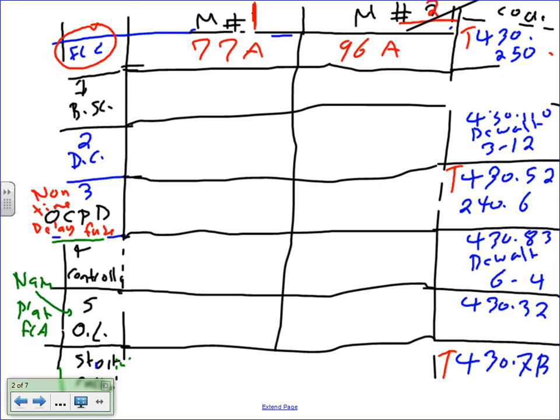430.22 here. So if you guys go to 430.22, and don't forget the table that got married, 310.15(B)(16). So that's changed because the table got changed. That's really not a big deal. If you guys go there, find the branch circuit. It's continuous load, 1.25. So Chris, you take the 1.25 multiplied by 77.